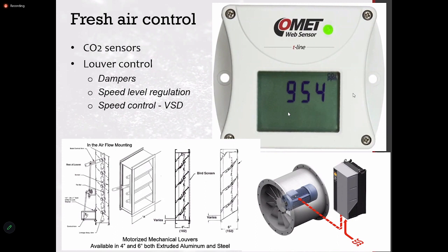So this is a CO2 sensor. This will be installed at the office space. This actually has to be installed at a very low space, as I got recently stuck installing this at the duct level. It was too high. So you have to install it at a table level, like a breathing space level, we call it, so that you actually get a proper reading of the CO2 level of the premises. And depending on the settings on this, you can send a signal to a motor controller and you can switch on the fresh air fan.